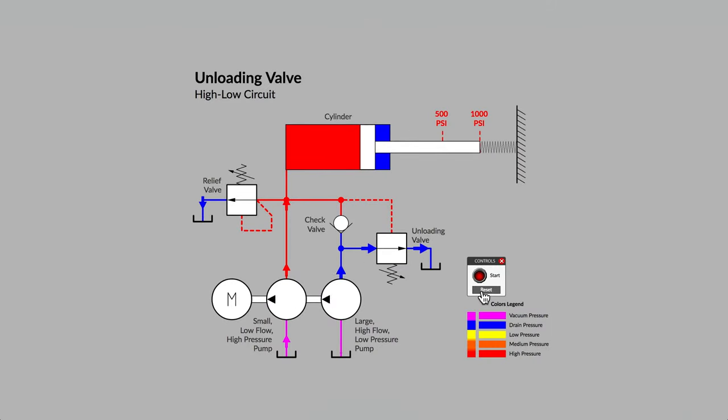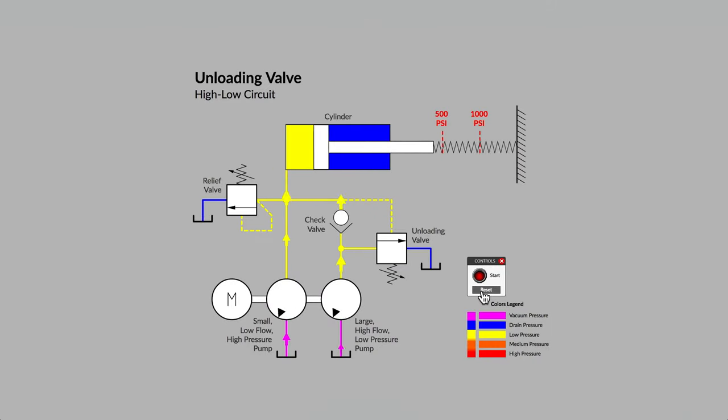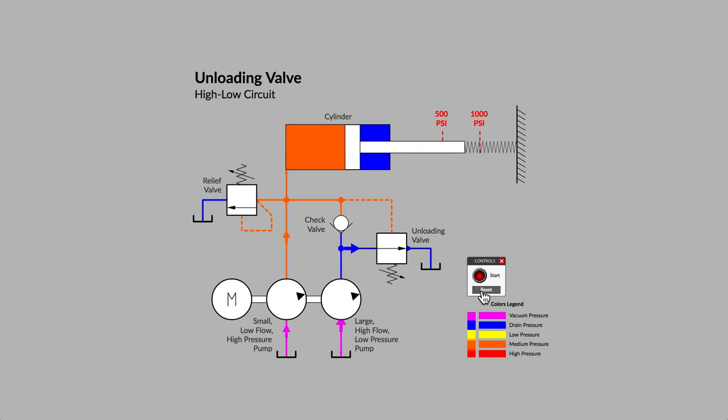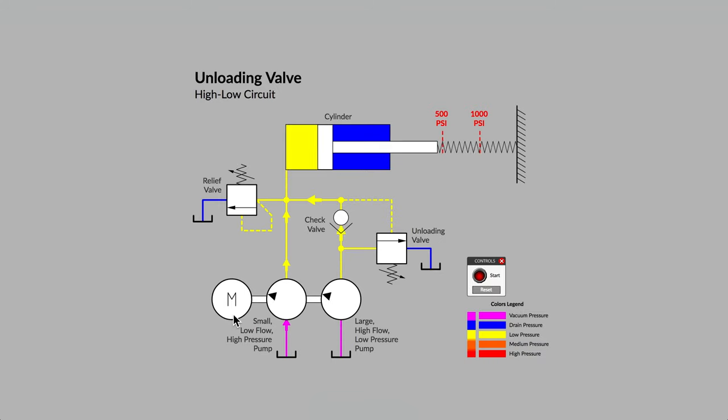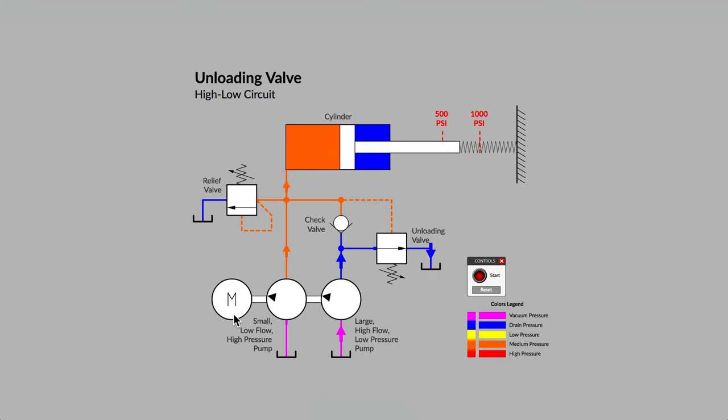It is not uncommon to find an unloading valve in use with fixed displacement pumps. An unloading valve can be used to create what is sometimes known as a high-low circuit, and it is also used to minimize the power required from the prime mover, an electric motor in this case, when the system pressure gets to a level that might cause the motor to stall.